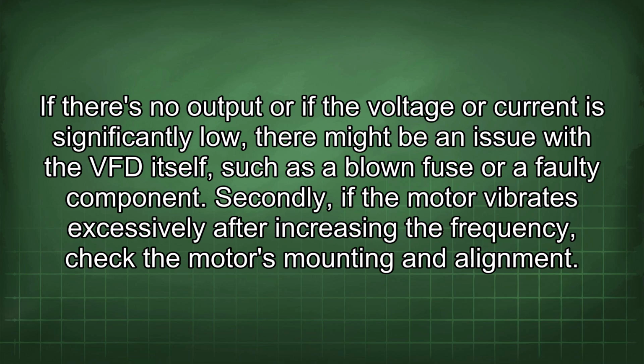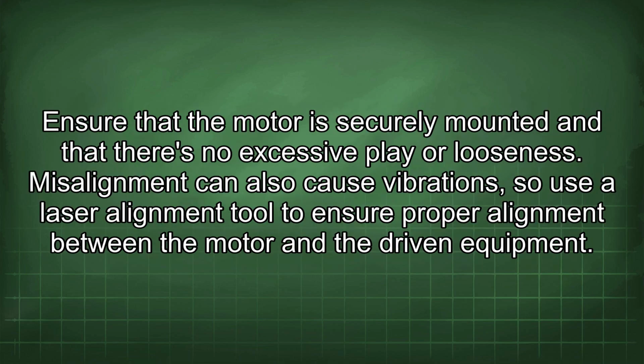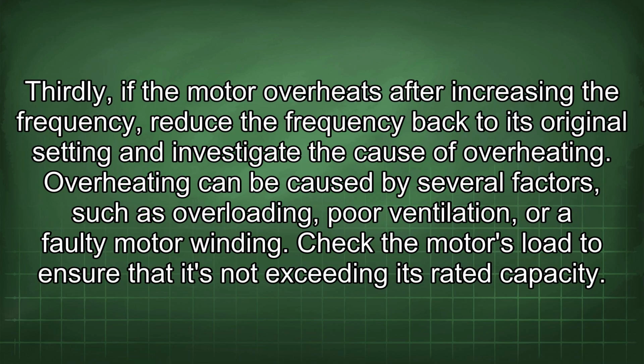Secondly, if the motor vibrates excessively after increasing the frequency, check the motor's mounting and alignment. Ensure that the motor is securely mounted and that there's no excessive play or looseness. Misalignment can also cause vibrations, so use a laser alignment tool to ensure proper alignment between the motor and the driven equipment. Thirdly, if the motor overheats after increasing the frequency, reduce the frequency back to its original setting and investigate the cause of overheating.